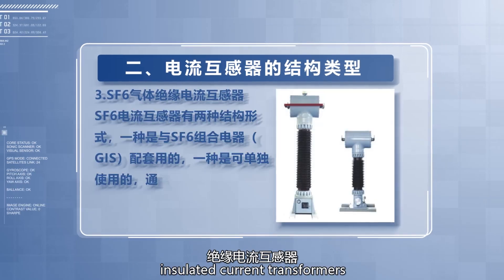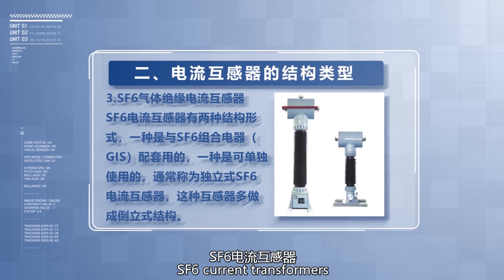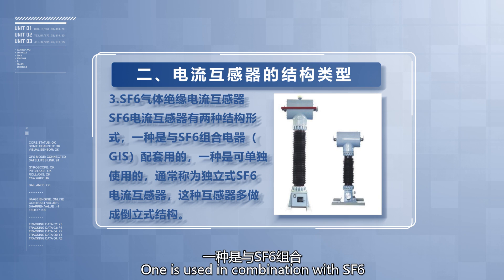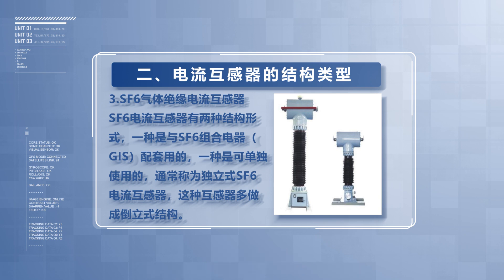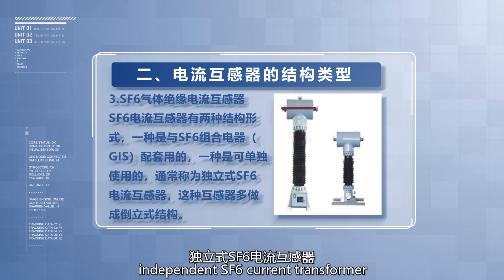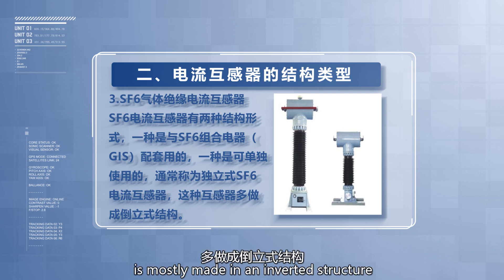SF6 gas insulated current transformers have two structural forms. One is used in combination with SF6 electrical equipment, and the other is the standalone type, commonly referred to as an independent SF6 current transformer. This type of transformer is mostly made in an inverted structure.